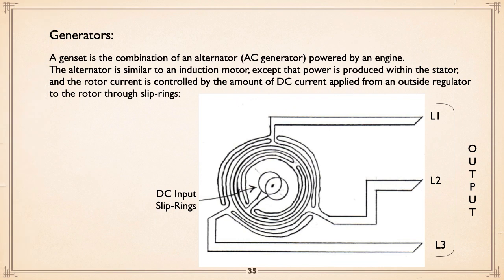Generators. And a generator, a genset, basically is an AC generator or alternator powered by an engine. The alternator is similar to an induction motor, except power is produced within the stator, and the rotor current is controlled by DC current applied externally, so through slip rings. So you're controlling the current and magnetism of the rotor to control voltage. And that's done by a DC power supply. But that basically is what you're doing. It's by controlling the DC input through slip rings to the rotor, you can control the output.